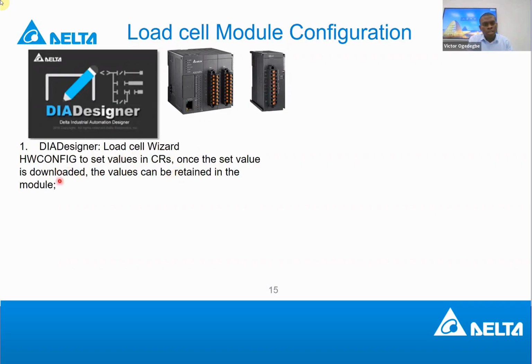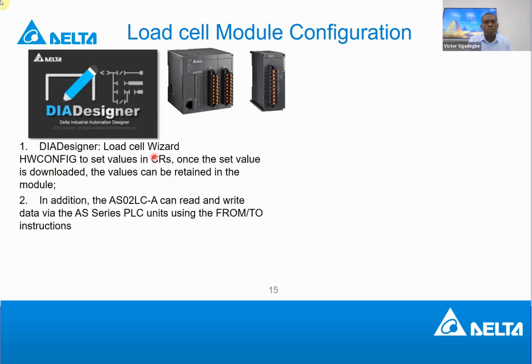One of the advantages is that if you do this in the load cell wizard and download it to the module, your configuration will be retained. It means that if you power off or lose power, what you have configured will remain and will not change. That is one of the possibilities you can use to configure the load cell module.